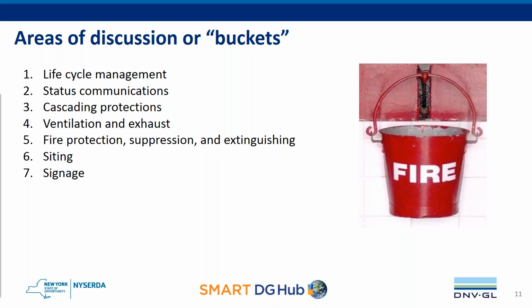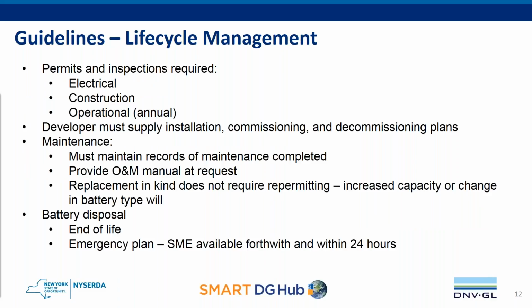Items 4 and 5, around ventilation, exhaust, fire protection, suppression, and extinguishing, are all about mitigating these catastrophic failures. So in case 1, 2, and 3 did not stop the issue from proceeding, the next items in the failure protections would be ensuring appropriate ventilation, exhaust, and fire protection. Finally, with 6 and 7, for siting and signage, the idea is that you site the system appropriately, so it's not putting any people or buildings or other items at risk, such as hazardous materials. And then signage will allow first responders or passersby to know what hazards may be in the area, as well as to have the contact information for a subject matter expert. So I'm now going to dive into the topics a little more specifically.